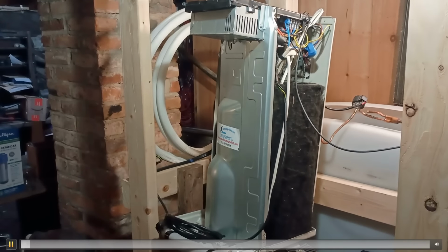So other options are to just use the ground source heat pump. The pros are they're very efficient. The efficiency is based on the temperature of the ground, and the ground temperature is quite constant. Another benefit of these systems is the heat output is not impacted by outside temperature. Like we saw that penalty for lower outside air temperatures, that's not a problem for a geothermal system.